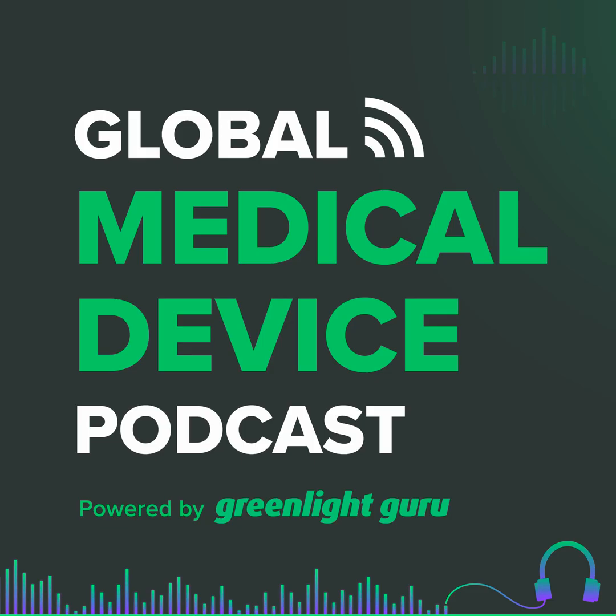One of the concerns that I have about the newest PCCP guidance that applies to all devices, and as an FDA consultant, I've expressed my concern to the agency on this already, is they make an explicit point that any changes that you make in your labeling, for example, have to be within the original indications of the clearance or approval.